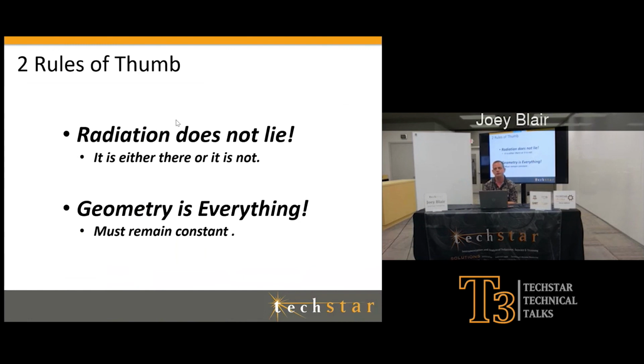I can even give you some examples. I've gone out to a vessel, and operations told me this vessel is 100% full, but my gauge is reading 0. There's something wrong with my detector. I guarantee you my vessel's full. Look, I have a sight glass, and it's saying it's 100% full. Heck, I have 2 sight glasses on this thing, and they're both reading the same thing. Everything I'm seeing says it's 100%. There's no way there is any process inside this vessel.